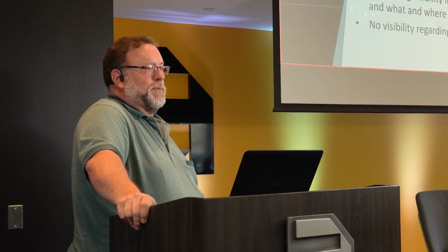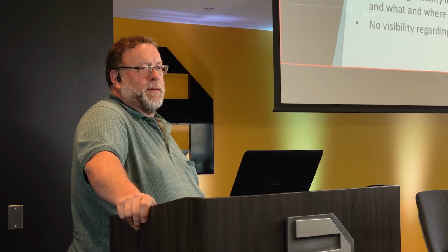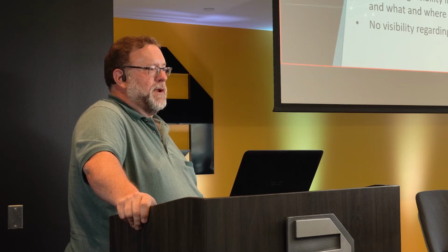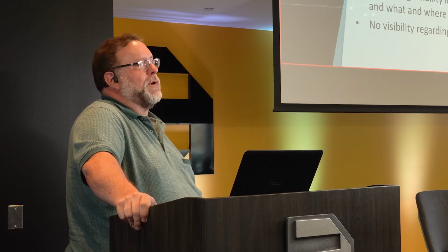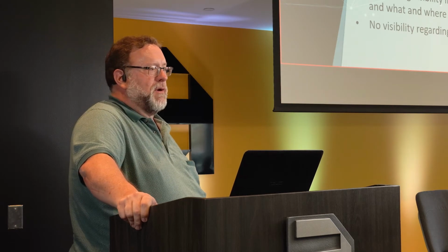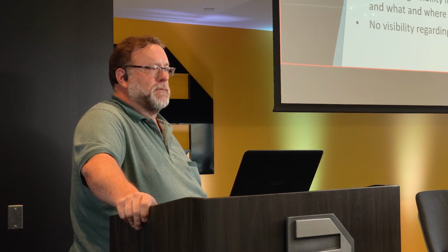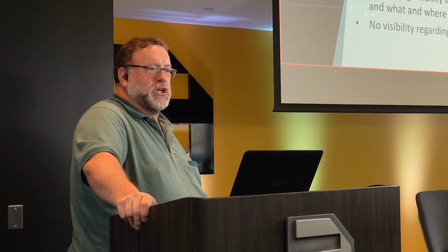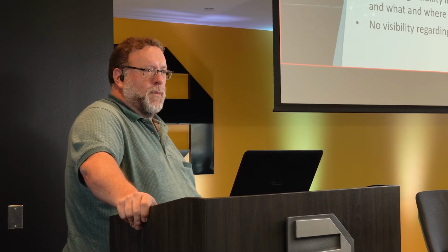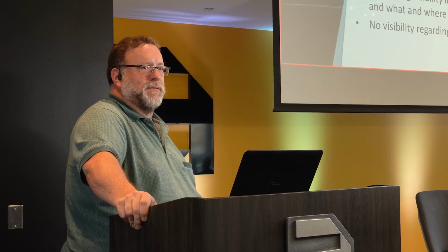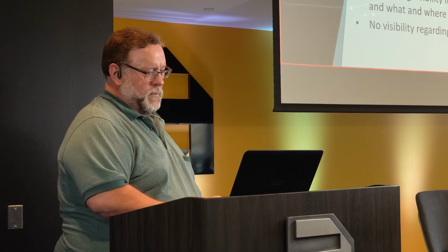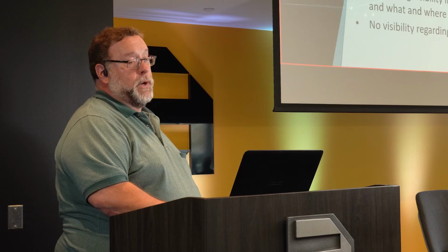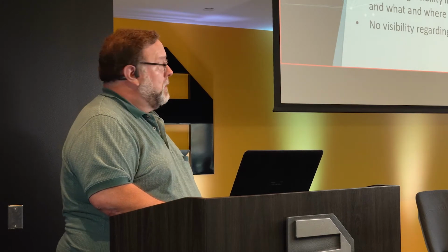So if they unplug their PC from this switch and run their laptop down to a top-of-OP10 switch and plug in there, and they try to reach a PLC back in OP40 across the network, it'll let it. It'll write a flow to allow that to happen, right? So it'll basically configure the network on the fly automatically. So it makes it super easy. You don't have to run around and configure switches ahead of time. They plug them in, power them up, pretty close to done at that point.